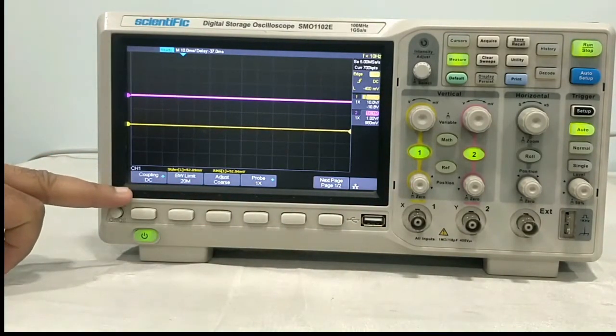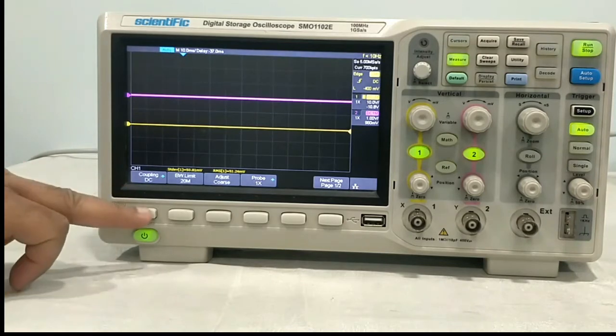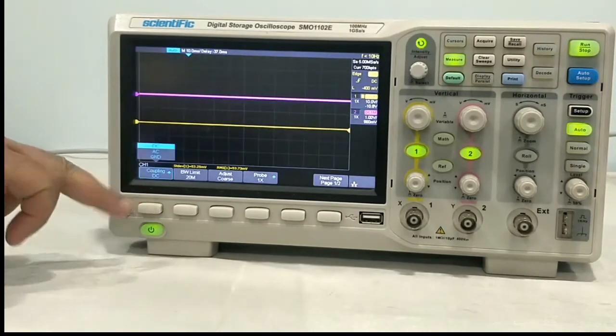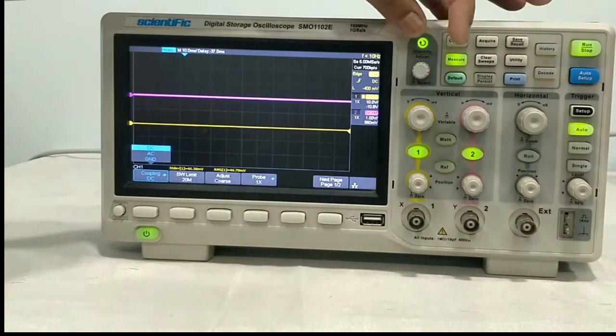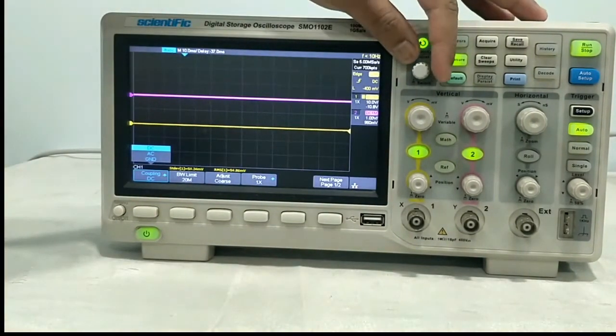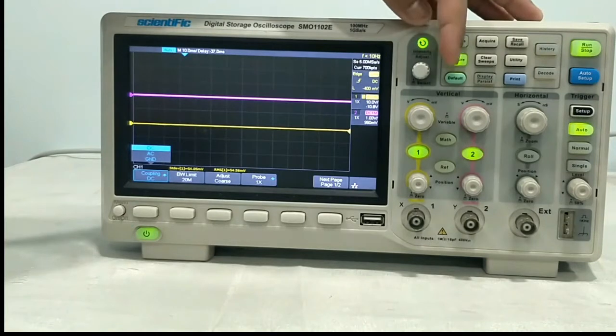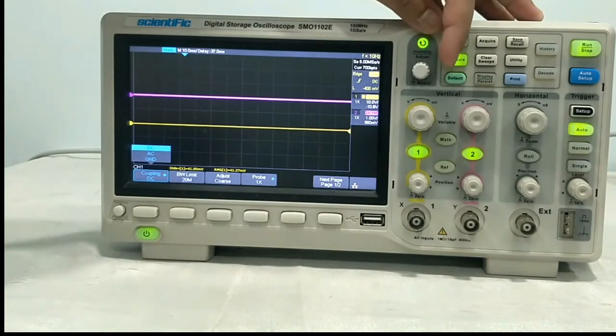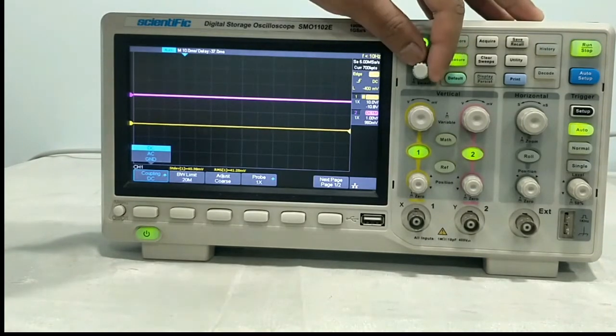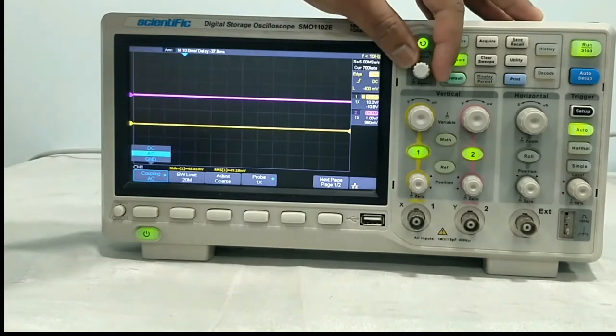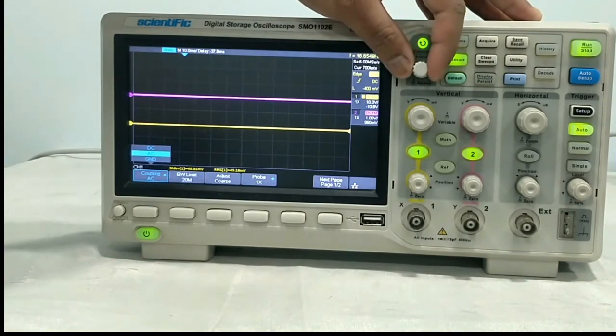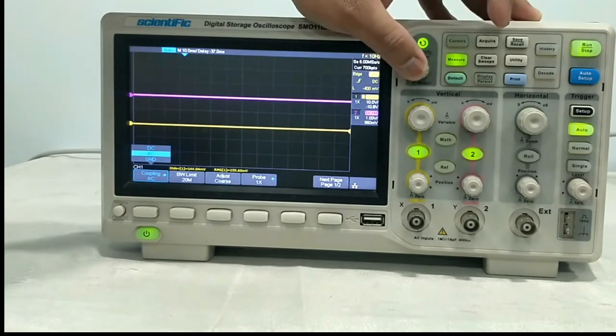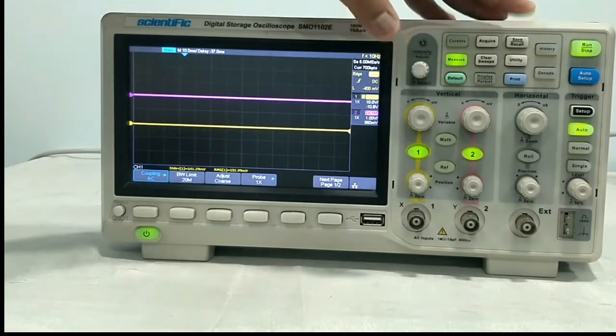The first option is coupling. Pressing this key, you can select the coupling. To set the coupling, you have to rotate this selection knob. You can find DC, AC, or ground. Right now we are putting it to AC.